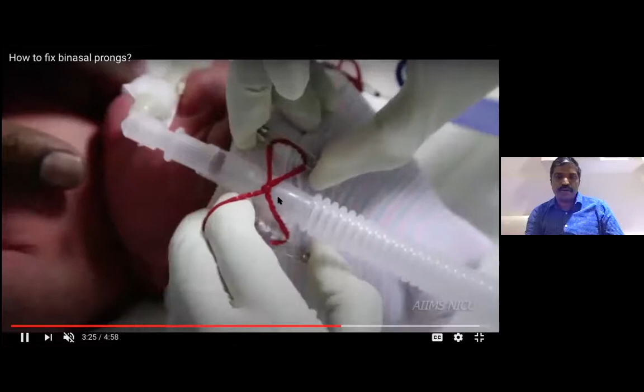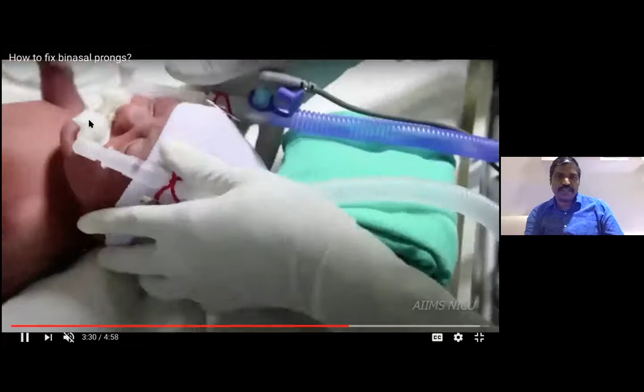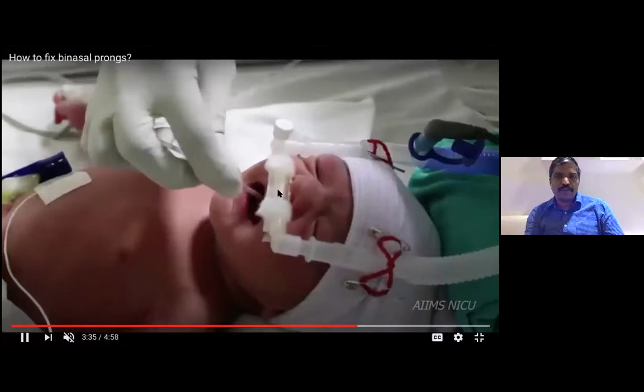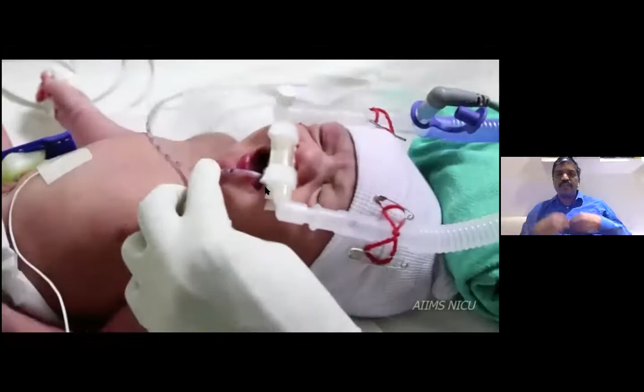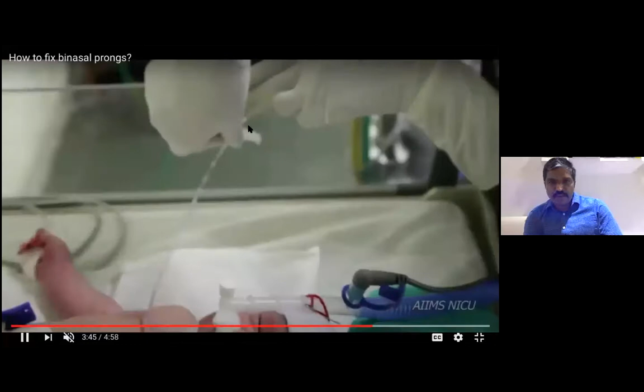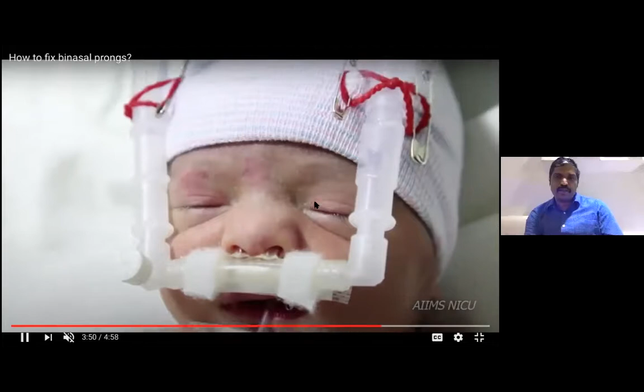Okay, do this on the same side. Now your bubble CPAP is connected to the patient. This is a patient interface connected. Now you should put an orogastric tube. After putting the interface, immediately you have to put an orogastric tube because you want to vent out the air which goes into the tummy and avoid bubble CPAP belly. And this should be fixed onto the side. The tip should be above the level of the tummy. So now the baby is comfortable.